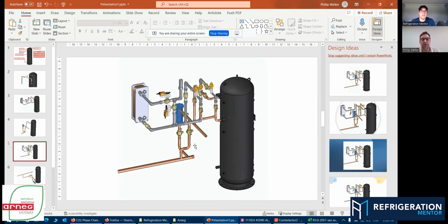Yeah. So here what we have right now, and I kind of like this, is you're starting to see it all come together, right? We just talked about this, and I think everyone can see that now, and it makes a lot more sense. The rack is starting to build out. So our two valves right here, one's redundant, flash tank, vertical flash tank. Here we've got that flash gas bypass valve. Here we've got our bypass, our suction filter. Here's our plate heat exchanger. Here's our suction manifold going back to the compressors.